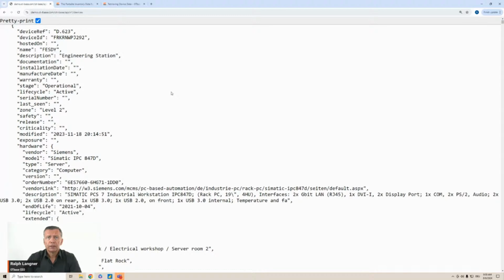If this information is set by the manufacturer, then it will be automatically extracted via EtherNet/IP. So you will see the manufacture date automatically, which is super important and helpful if you consider Rockwell product notices, because most of the time they will be tied to devices with a specific manufacturing date range.